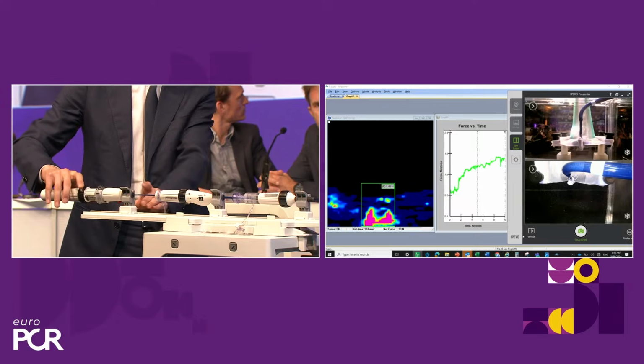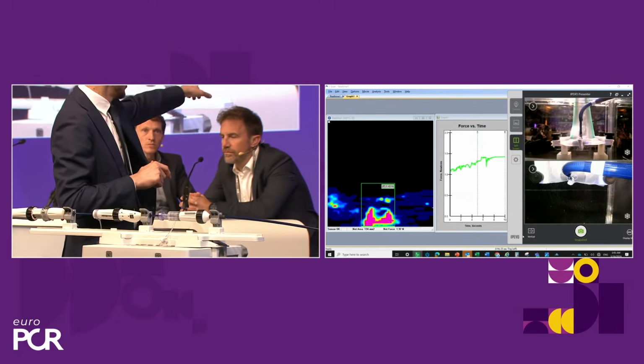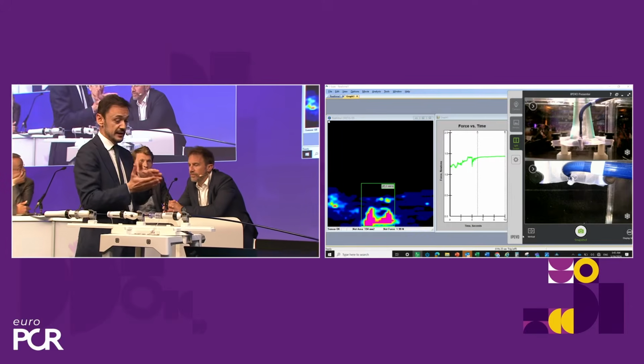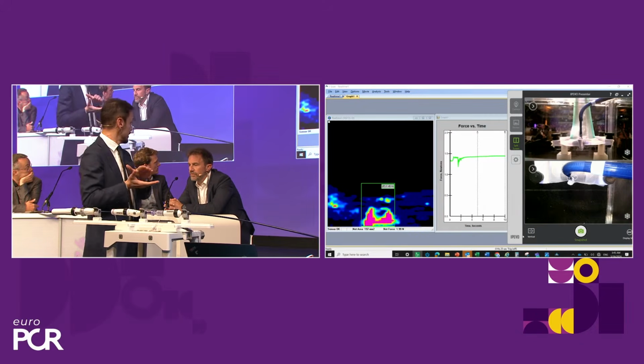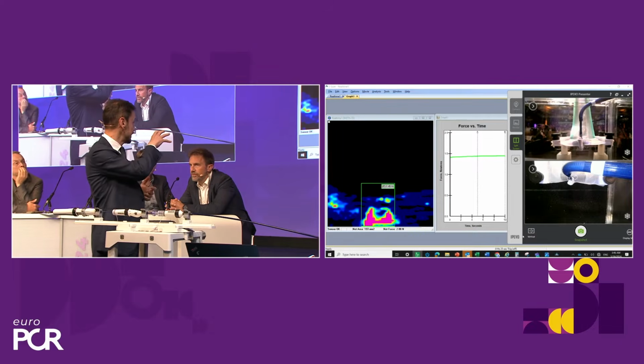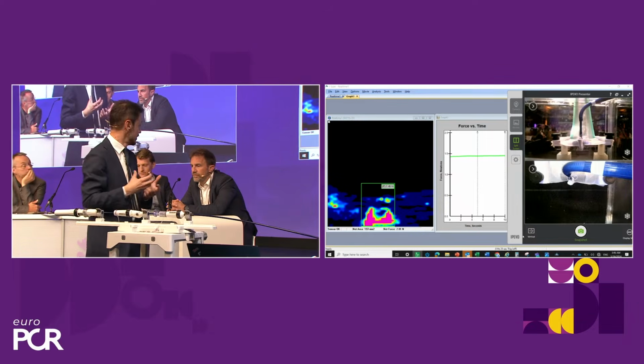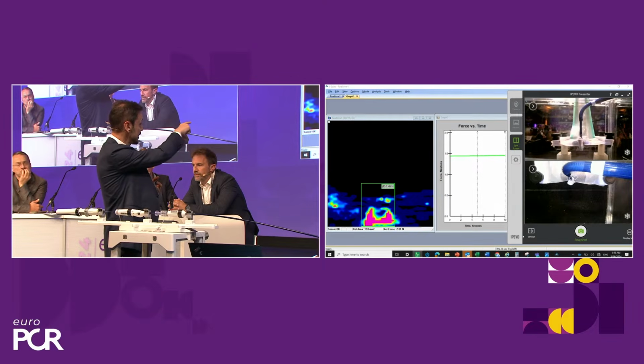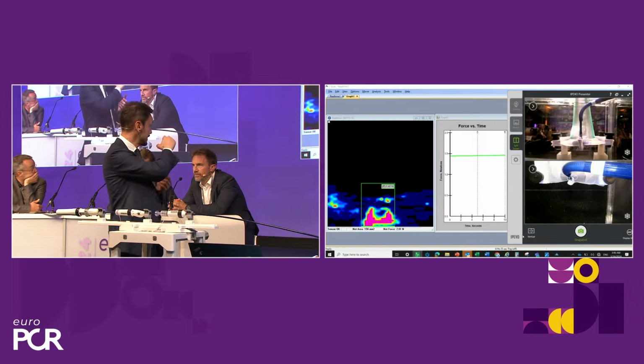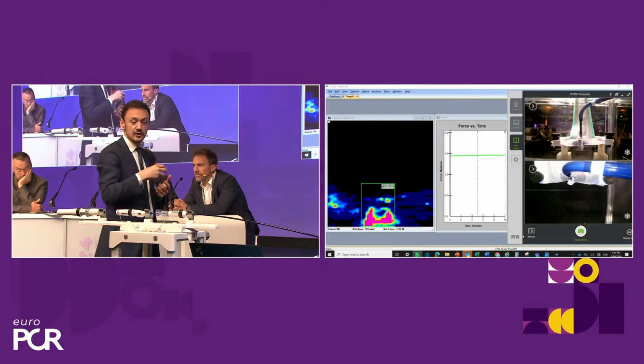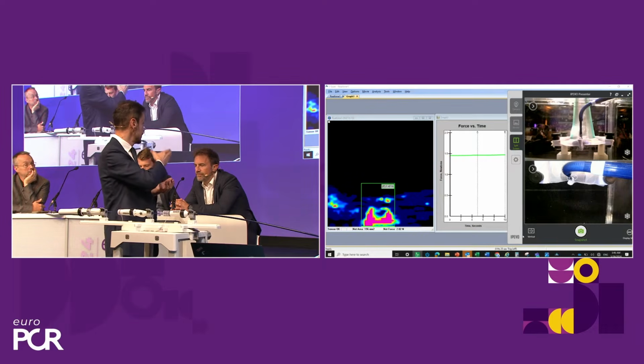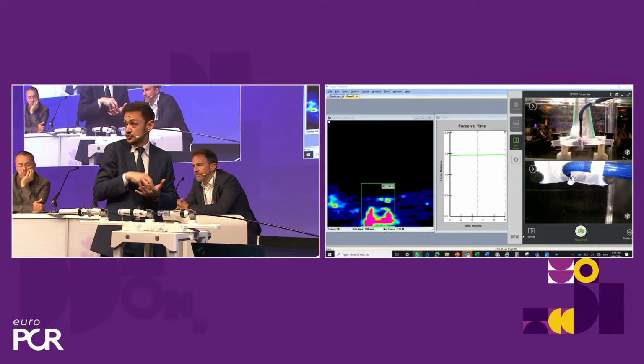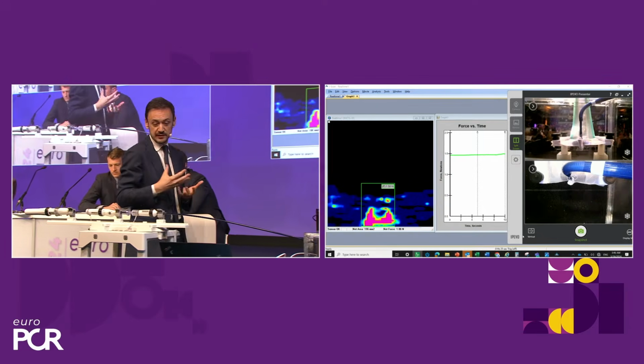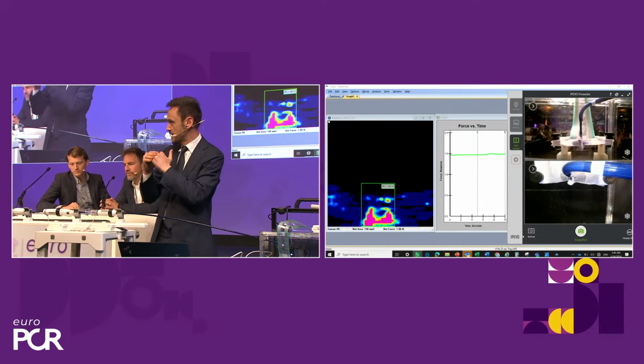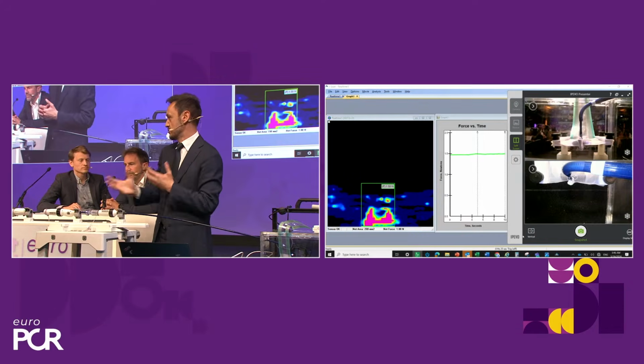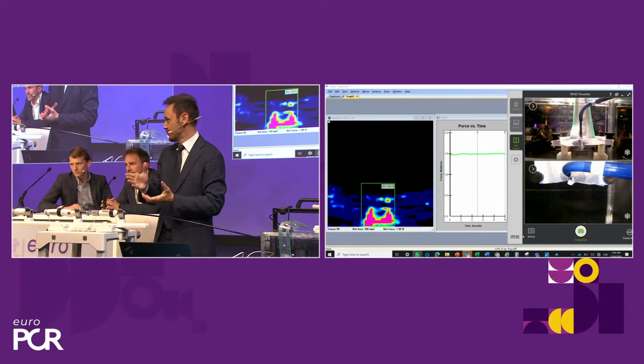And you see that the red is distributed on the surface where the leaflet is inside the paddle and the clasp. So there is no other portion of the leaflet where there is tension or force applied. And it is extremely stable over time. So it goes up, and then it stays stable without any non-uniform distribution. So it is stable, it is uniform, it is localized where it should be localized. And this should ensure that we do not damage the leaflet. So we have stable retention, but atraumatic. So it is the combination of what we actually want to have when we perform this procedure.